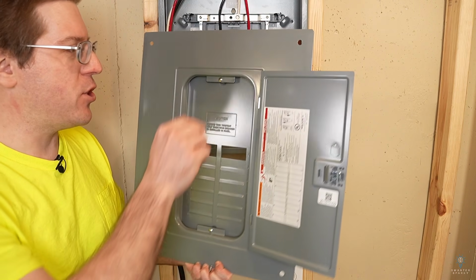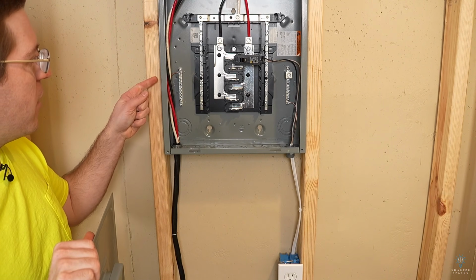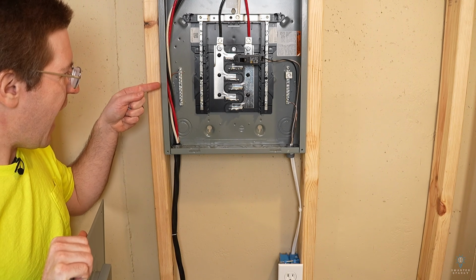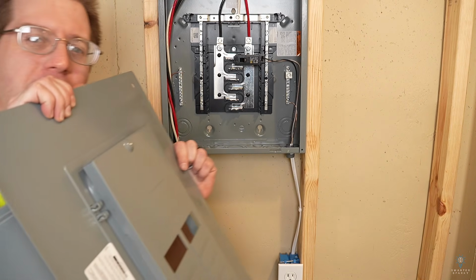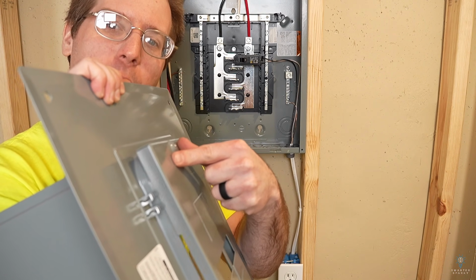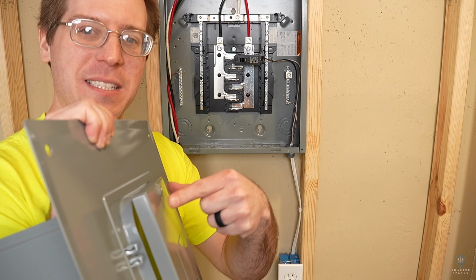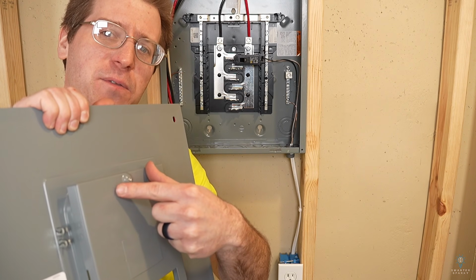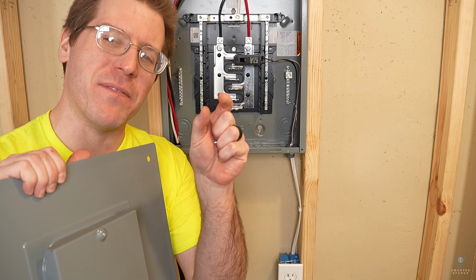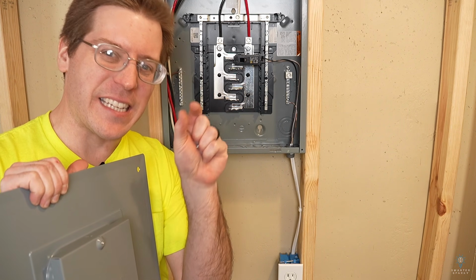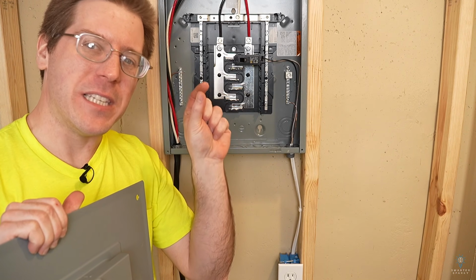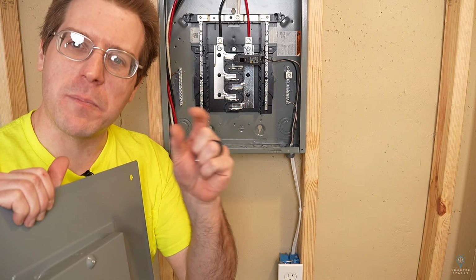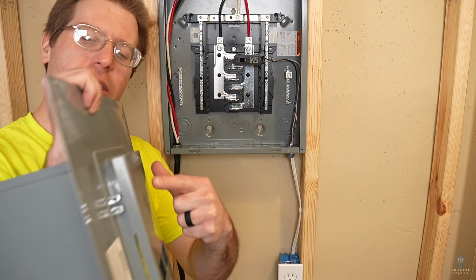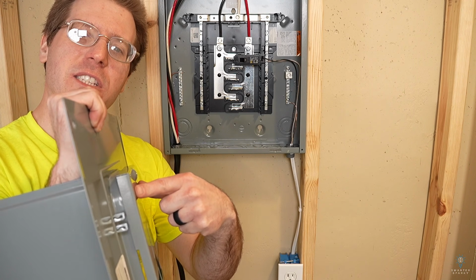Another thing I wanna mention is, remember at the beginning of the video where I showed to measure that 1/2-inch distance there? A lot of newer panels actually come with a spring-loaded dead front piece here on the cover. It's actually kind of a nice little feature. It will actually make up for some of that distance if there is a slight discrepancy between how deep the panel is in the wall and how much space there is to make up between that. There is a little bit of leeway there because of this spring-loaded cover.